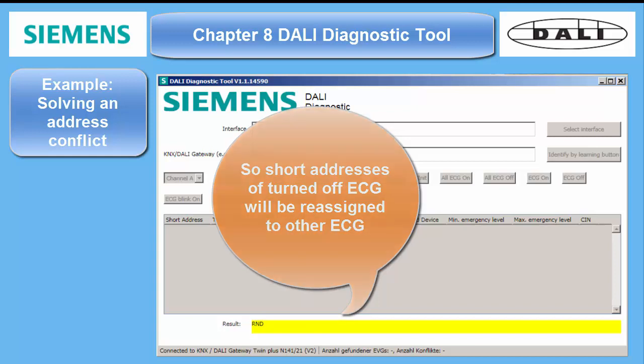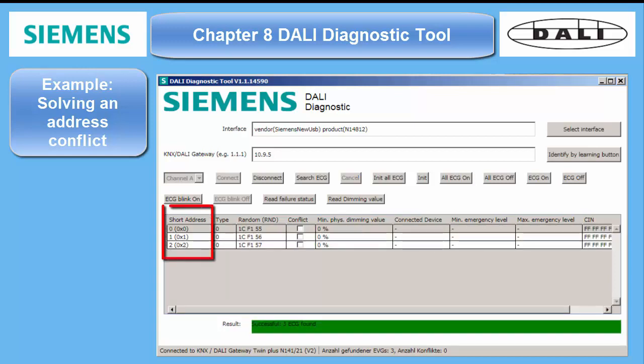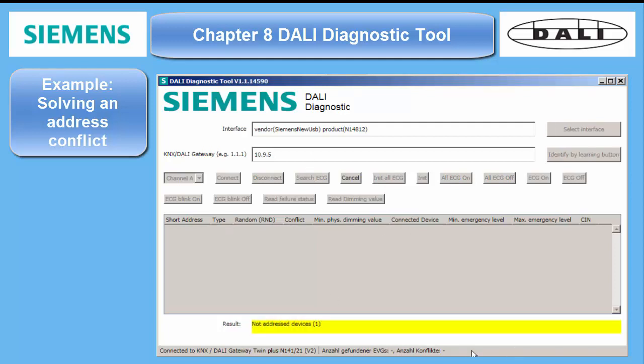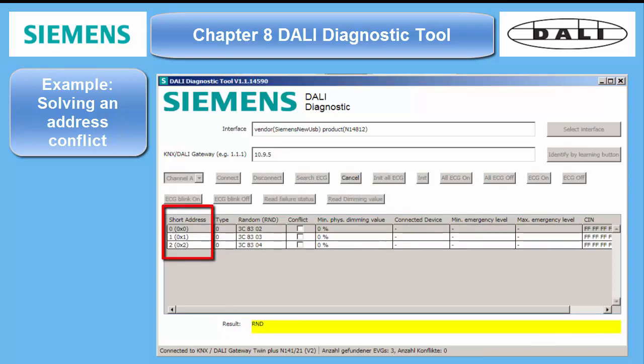ECGs bearing ambiguous short addresses will be initialized — meaning the short address will be erased and set to 255, and the long address will be randomized once more. These initialized ECGs will then be assigned new short addresses in ascending order. In my sample, I initialized only three ECGs; they received short addresses 0, 1, and 2. I then switched them off and initialized another set of three ballasts. They also received short addresses 0, 1, and 2, but with different random addresses. When I turned them all on together and scanned the bus again, the result was a triple address conflict.